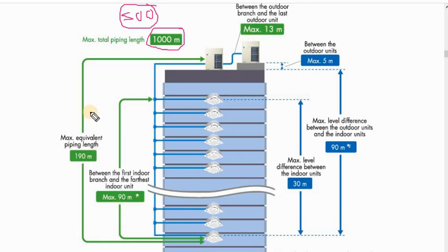The second one is from the outdoor unit to the last indoor unit, the maximum equivalent piping length should not be more than 190 meters. Okay friends, this is the limitation. The next one is between the first indoor unit branch and the farthest indoor unit. From the branch to the farthest indoor unit, it should not be more than 90 meters, but mostly we are using 40 meters. For this 90 meters we have to make some changes in the piping. We have to increase the diameter to get the 90 meters. Mostly we are doing below 40 meters. I will show you how we can go up to 90 meters also.